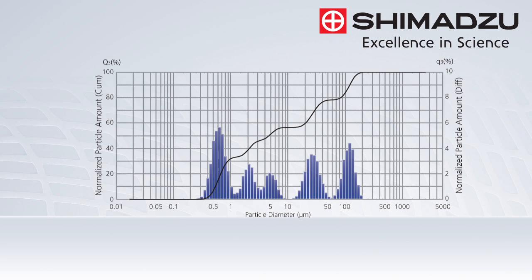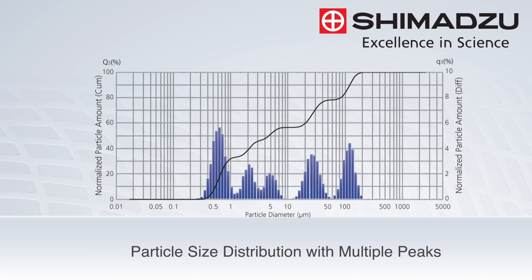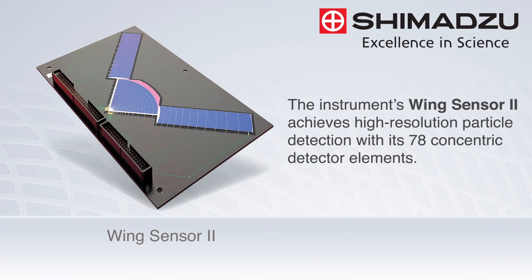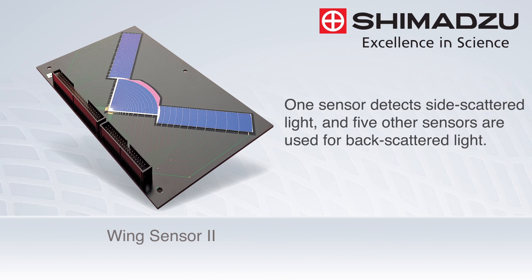Some complex samples may contain several particle size distributions. With its high resolution capabilities, the SALD2300 enables the acquisition of data with multiple peaks. The instrument's Wing 2 sensor achieves this with its 78 concentric detector elements — one sensor detects side-scattered light, and five other sensors are used for back-scattered light.